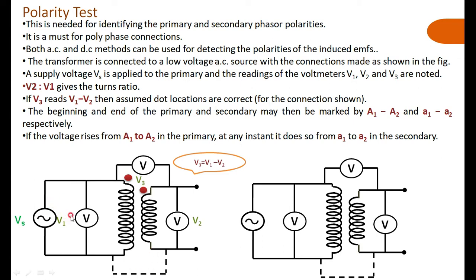You can notice the values of V1, V2, and V3. If voltmeter V3 reads the difference V1 minus V2, then the polarity connection is such that at any given instant of time the voltage is rising in the primary and the potential is also rising in the secondary — therefore you get a difference of V1 minus V2. At any given instant, if the primary is positive, the secondary is also positive, so V3 reads V1 minus V2.